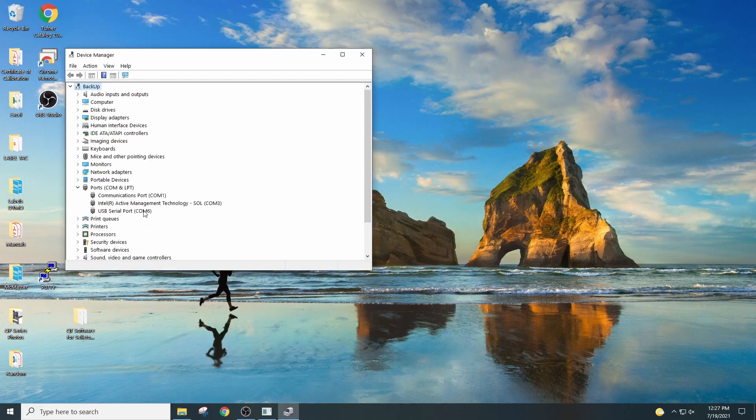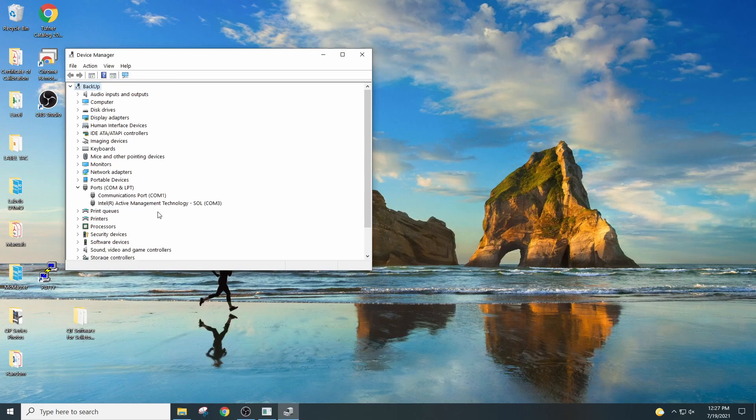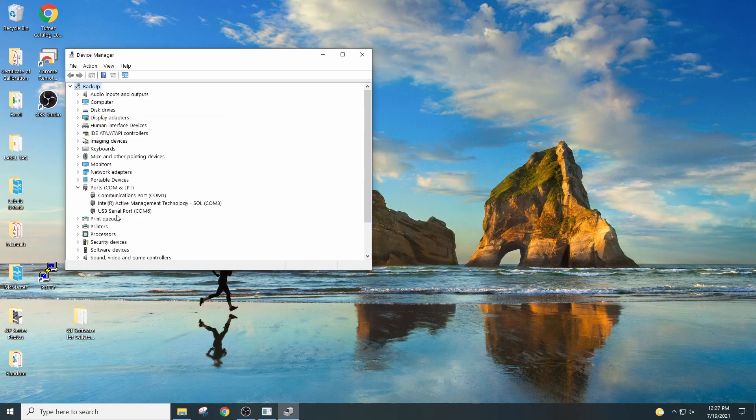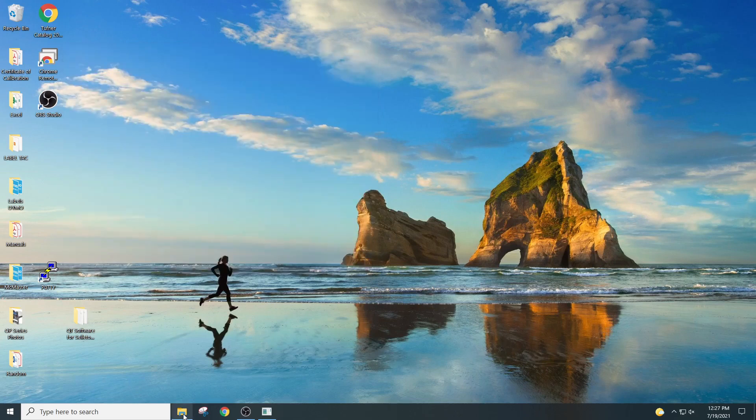You should be able to click on Ports and mine is currently port 6 or COM 6. To check, you could actually remove the USB cable from your PC. The indicator does not have to be on for this, but unplug the USB. You notice how I only have COM 1 and COM 3, but when I plug in my DB9 to USB cable to my desktop or laptop, then COM 6 appears. Now I know my OP900 is on COM 6.